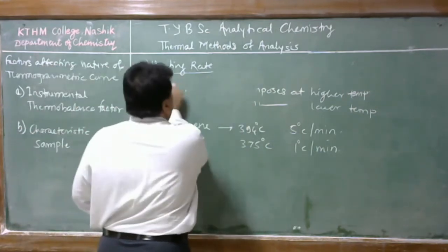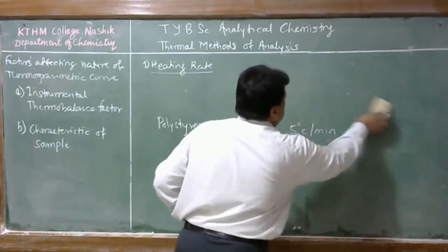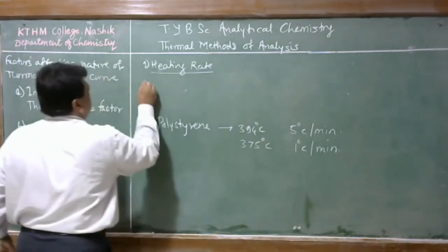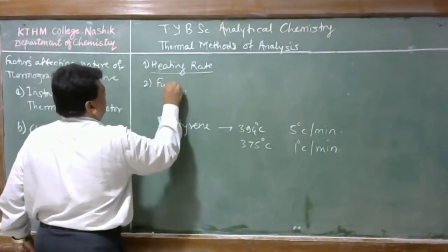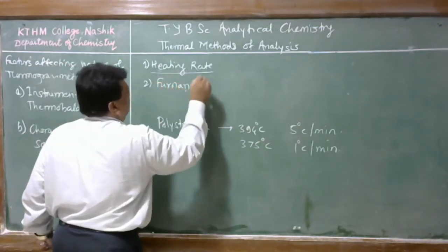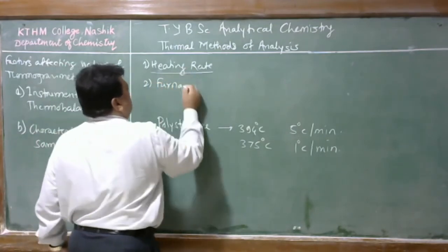The second factor, with heating rate, is furnace atmosphere. Not furnace temperature, furnace atmosphere.